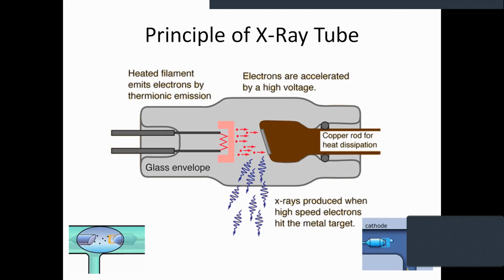The wavelength of the X-rays depends on the target material and the velocity of the electrons hitting the target. X-ray equipment for diagnosis uses target voltages in the range of 30 to 200 kilovolts, and the current in the range is several milliamperes.